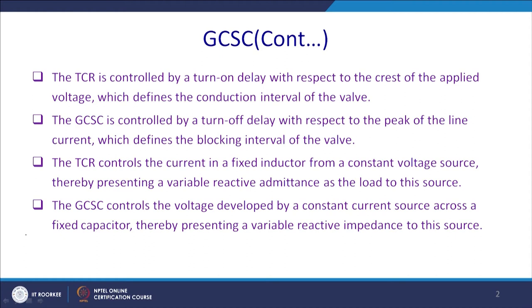The TCR — that is the thyristor controlled reactor — is controlled by the turn-on delay. Please recall your TCR in shunt compensation with respect to the crest of the applied voltage, that is at the peak of the applied voltage, which defines the conduction interval of the thyristors or GTO, or what can be termed as a valve — because it can be a combination of series and parallel combinations to meet the voltage and current requirements.